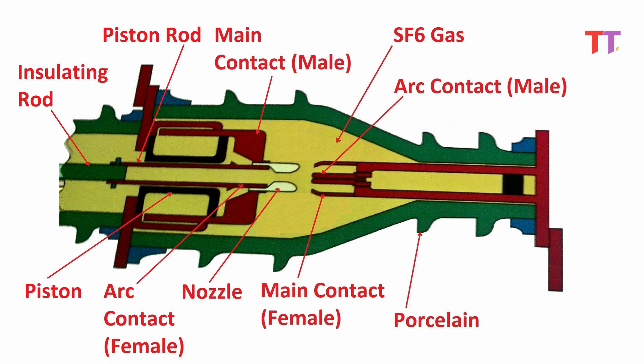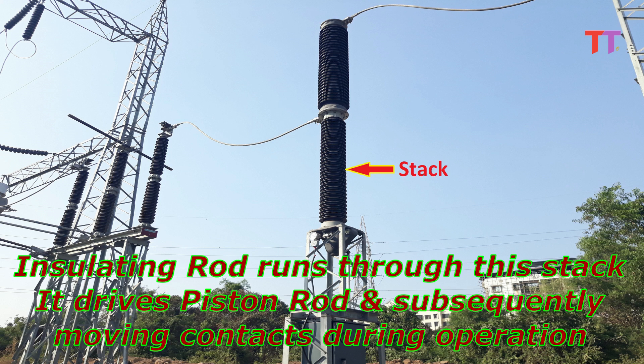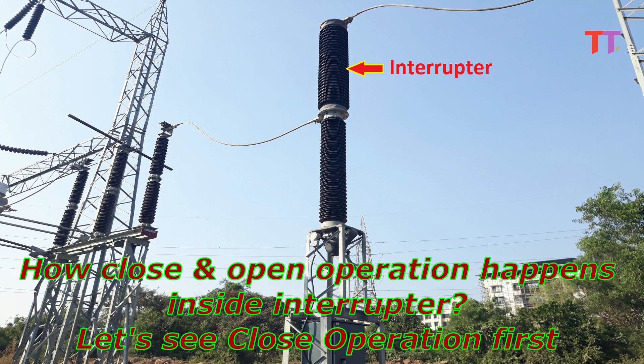Piston rod is coupled with insulating rod. This is how insulating rod looks like. Which runs through this stack and drives piston rod and subsequently moving contacts during operation. So let's see how close and open operation happens inside interrupter.